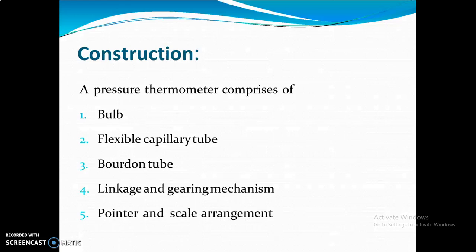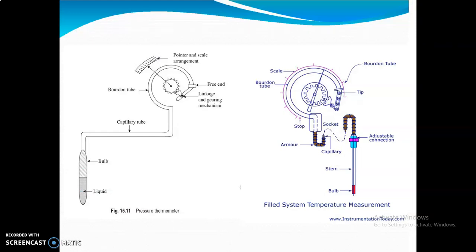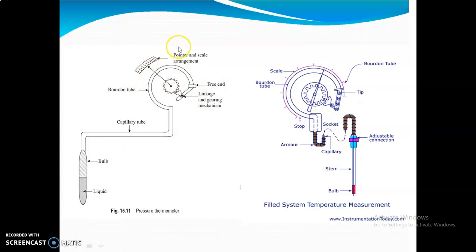The pressure thermometer consists of several components: a bulb, a capillary tube, a Bourdon tube, a linkage and gearing mechanism, and a pointer with scale arrangement. Looking at the diagram, the liquid is kept in one part and is heated. The liquid expands or contracts, and this action is directly connected via the capillary tube to the Bourdon tube. One end of the Bourdon tube is a free end; the other is connected via the linkage and gearing mechanism, which consists of a spring with a pointer and scale arrangement.